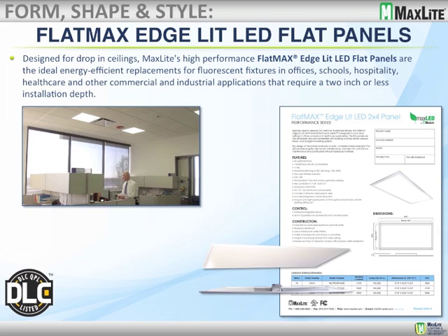Regarding occupancy sensors: all of these panels are compatible. For on/off occupancy sensing, you use your motion sensor by breaking in on the AC side — each driver has a standard three-wire AC connection just like any other light source. For high-low motion sensing, where you want, say, 50% light when no one is present and 100% when occupied, there are 0-to-10 volt occupancy sensors available. We'd be happy to work with you to find the best 0-to-10 volt high-low occupancy sensor for your application.